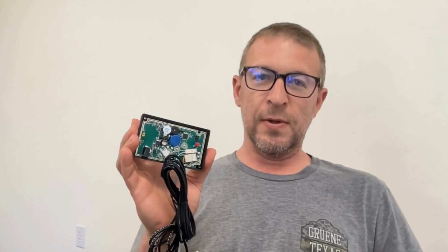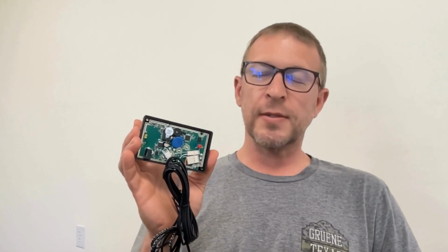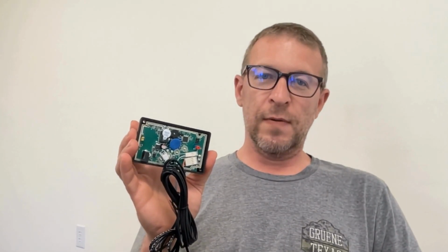And that's because with this pump, it does make some noise, and we wanted to reduce the number of off and on cycles. It's only adding about a tablespoon of water, but if you have a very small system, that could be an excessive amount of water being added.